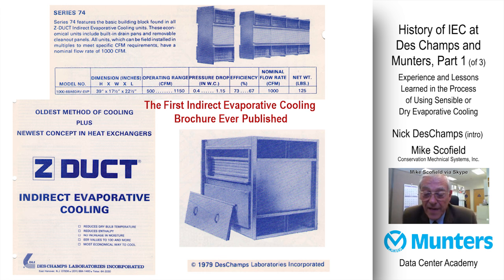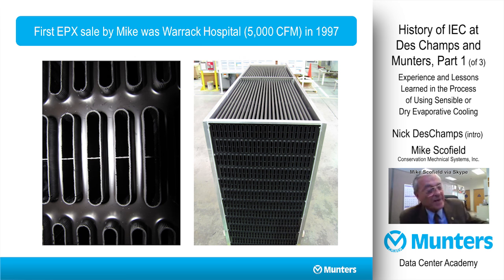And if the leaking got really bad, what the owner pointed out was instead of an indirect or dry evaporative cooler, he had instead purchased a very expensive direct evap cooler because both sides were getting wet due to air leakage. So we needed to find a solution to air and water cross-contamination between the wet side and the dry side. I think that the new polymer tube heat exchangers, which the beta site for the EPX technology was in 1997.